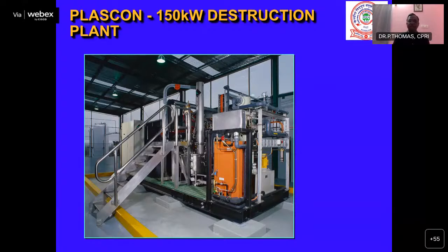You cannot retrofill. Retrofill, as you all know, means you remove the oil, clean the transformer, put back new oil, and start using the transformer. That is not possible for a transformer having 10,000 ppm and above. That is possible only with less than 10,000 ppm. Of course, there again we found that it requires a lot of flushing. You have to flush with new oil, maybe 2 or 3 times. Again, the cost will go up.